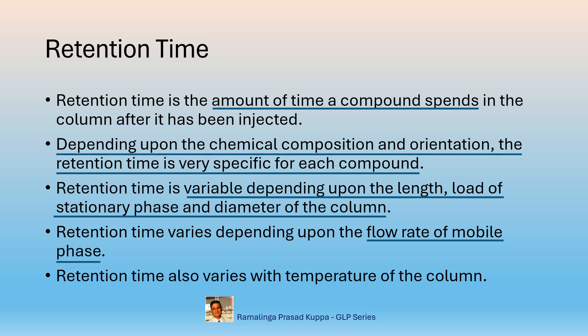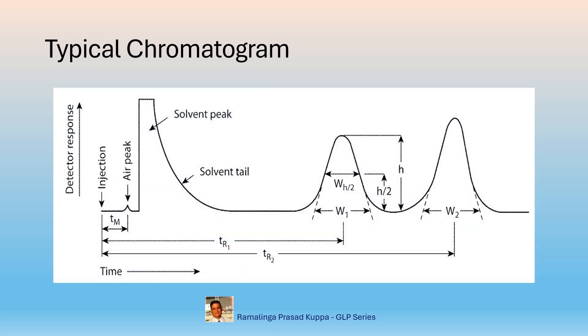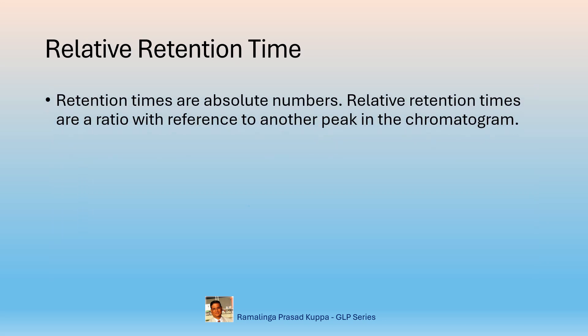Retention time also varies with temperature of the column. More the temperature, lower the retention time; and lower the temperature, longer the retention time. This is a typical example extracted from USP chapter 621. Retention time is measured from the point of injection to the midpoint of the peak where maximum height is achieved. Retention times are absolute numbers. Relative retention times are a ratio with reference to another peak in the chromatogram. Relative means where the peak appears with reference to another peak, so it is a relative term.